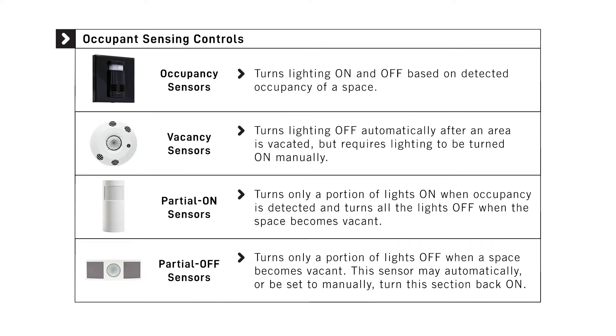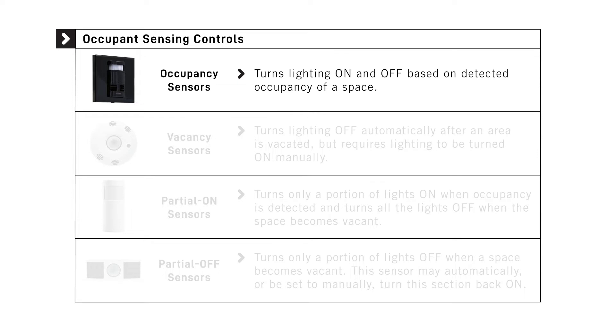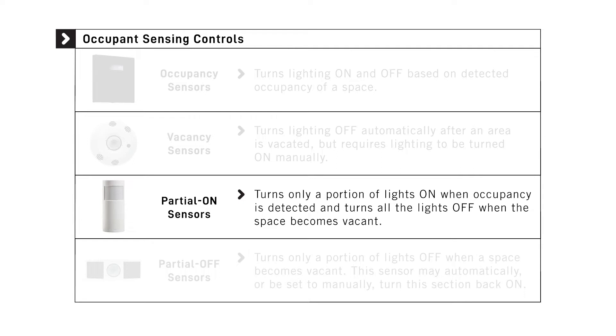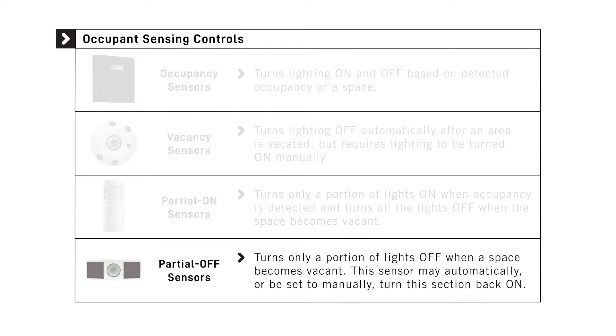Occupant sensing controls include occupancy sensors used to turn lighting on and off based on detected occupancy of a space; vacancy sensors used to turn lighting off automatically after an area is vacated but requiring lighting to be turned on manually; and partial-off sensors, which turn only a portion of the lights off when a space becomes vacant. The sensor may automatically turn this same portion back on, or the system may be set so that manual on control is required.